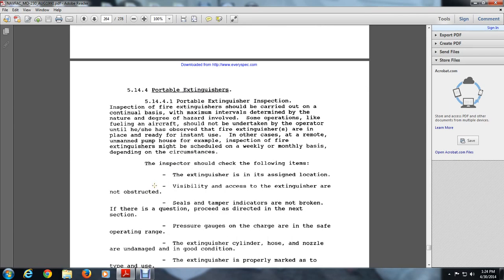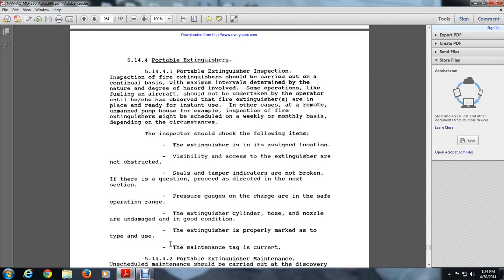The inspector should check on the following items. The extinguisher is in its assigned location. Visibility and access to the extinguisher are not obstructed, seals are not tampered with, and indicators are not broken. The pressure gauge is in the safe operating range, and the extinguisher cylinder, hose, and nozzle are in undamaged condition. The extinguisher is properly marked as to type, and the maintenance tag is current.